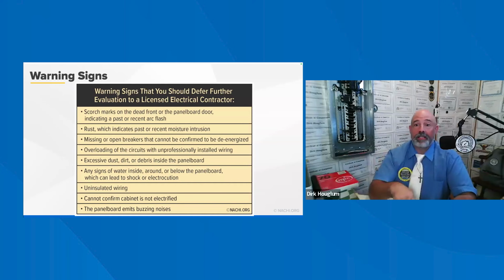There are warning signs that a panel board or cabinet or box of the system in general may be compromised. These signs indicate to an inspector to defer. So scorch marks on the dead front cover, rust, missing or open breakers, overloaded circuits, and excessive dust and dirt and debris. A lot of times I will find, I live in Florida, so I see geckos a lot in there, dead ones. Any signs of water inside the cabinet, that is bad news. Stay away from it. Don't open it up, because that could lead to shock or electrocution.